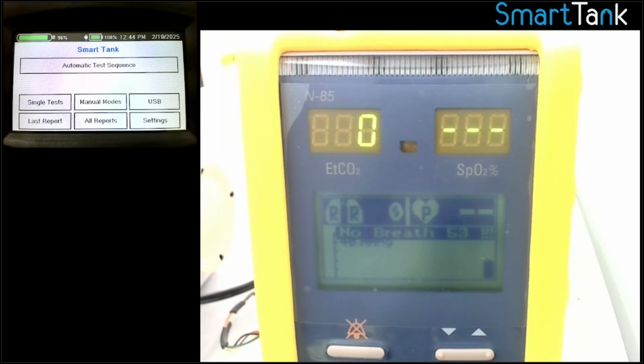We do have some questions. Great. One question is, can the SmartTank help test anesthesia monitors? Correct. So the anesthesia monitor, yes, not the vaporizer. So people get confused on that. It's not going to analyze the vaporizer and its output. What some of our customers will do is calibrate their monitor and then use the monitor to check the vaporizer. Knowing that they just calibrated it, they'll use that as the sensor to check their vaporizer. So the only thing is you have to just change the bottle out to the right gas in order to do the anesthesia monitor testing.